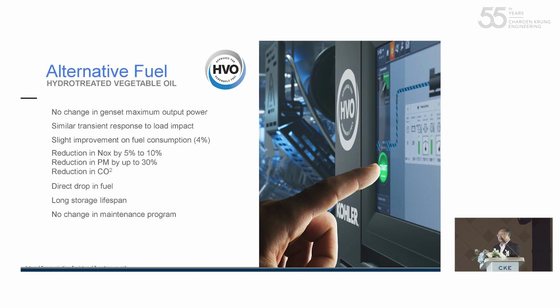The difference is in how it's refined. HVO is refined to provide a compound much better than biofuel, with characteristics very similar to diesel. This means it can mix with diesel in the fuel tank and operate the genset on its own at any percentage—70% HVO with 30% diesel, 100% HVO, or even 10% diesel with 90% HVO. It will still work without any modification.